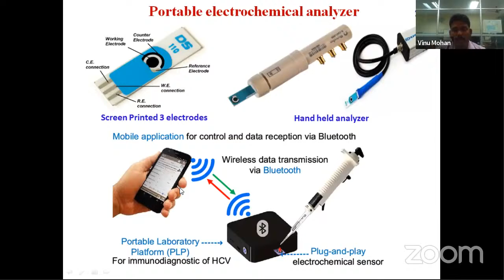So, especially for wearable electrochemical sensing applications, we are using two techniques: amperometric detection and potentiometric detection. The reason is we can easily prepare the controlled electronics. These screen printed electrodes, we need to connect with some PCB circuit board. In amperometric detection, it's very simple. We have to apply some constant potential and measure the current response. In potentiometric detection, there's no need to apply any potential, but we have to measure the open circuit potential at zero current. These two techniques, especially amperometric detection, we can use for all enzyme-based sensors.